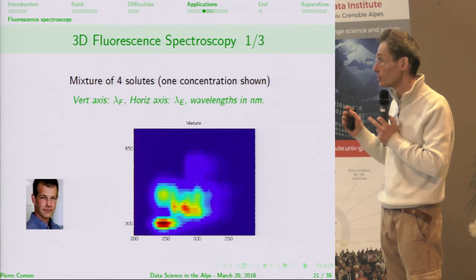So you excite the solution with light as a function of the wavelength of the excitation light. And the solution is emitting light in turn at a lower energy level, so at a larger wavelength. And this is the intensity. You have a matrix here. That's a matrix. It's not a tensor. But you can make several measurements. Assume that you want to monitor the tap water. So you can make one measurement in the morning, one at noon, one in the evening. You have 3 measurements. It is very unlikely that the relative concentrations are exactly the same morning, noon, and night, right? So you have slightly different concentrations. So this gives you a tensor with 3 matrix slices, and you can compute the CP decomposition.